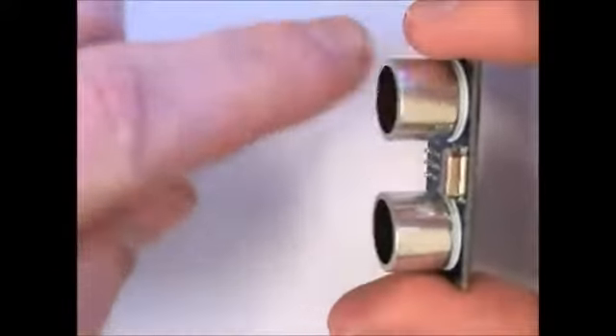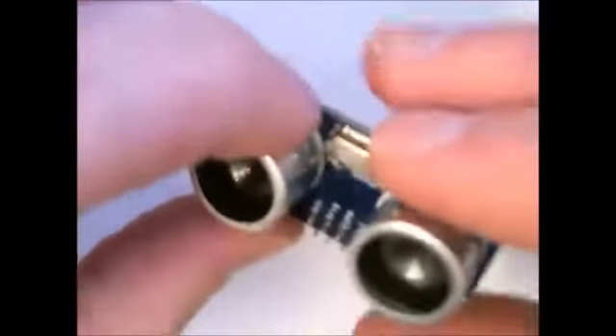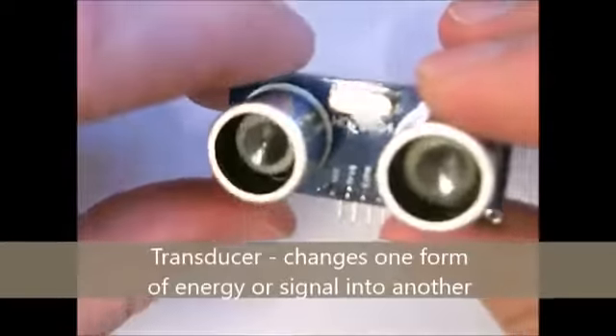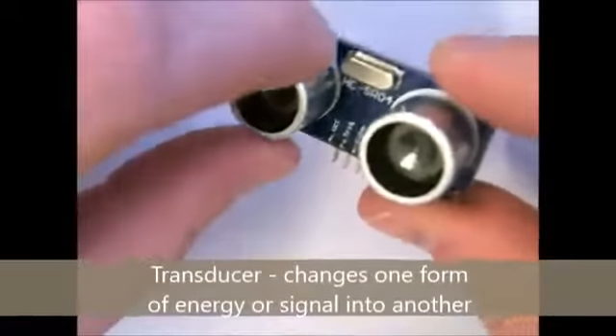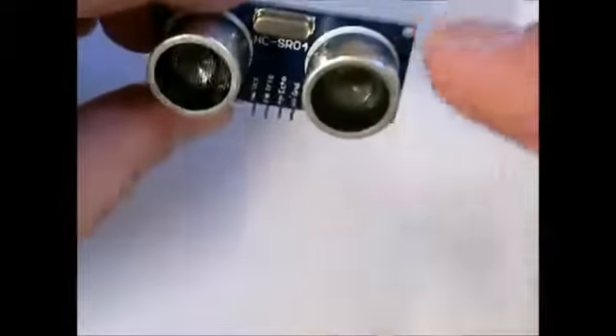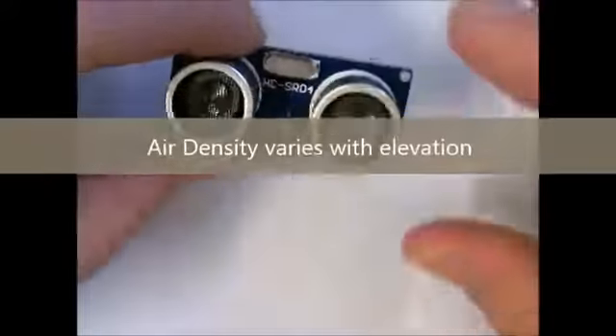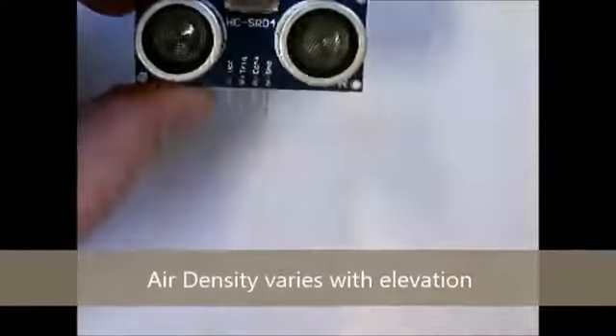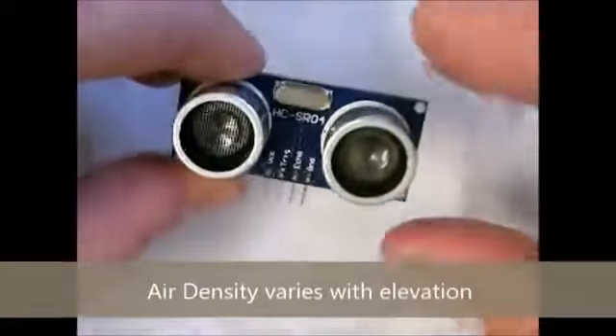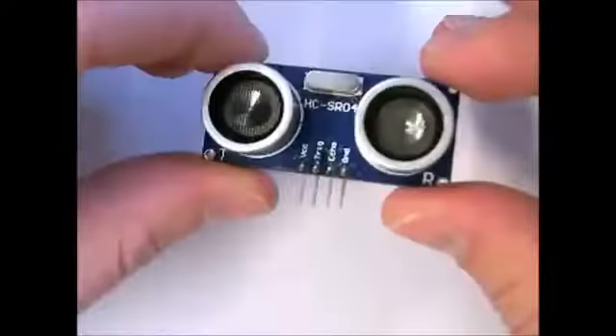Ultrasonic sensors work by sending out a signal from one of these transducers, called ultrasonic transducers. They send out an ultrasonic signal and measure the time for that signal to go out, hit something, and come back to be received by the other transducer. By measuring that time, and based on the density of air, you can figure out how far away the object is. That's why these are generally called range finders.